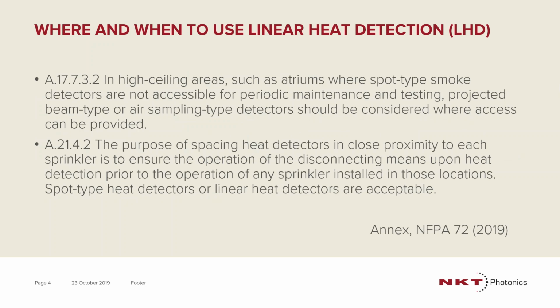So where and when to use linear heat detection? This is an annex of NFPA 72 stating the conditions of use of linear heat detection. Typically, you have high ceilings and atriums where smoke type and spot type detection is not readily accessible for maintenance. You may use alternative forms of detection, such as beams, air sampling, linear heat detection, as well as in conjunction with sprinkler systems, using linear heat detection as a cross method of detection for your water sprinkler system.